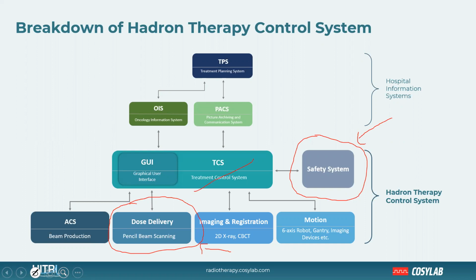Even if TCS crashes, for example, these two would monitor if the doors are open or closed, what's the currently delivered dose, whether it has already reached the prescribed level or not. And even inside they have redundant 2 ionization chambers, just in case one would give erroneous feedback. They have 2 either CPUs or 2 chips that kind of monitor everything. So this is kind of a simple answer. So when it comes to real-time delivery of the dose or even motion, you don't want to rely on particularly high-level software, but you want to do it with hardware devices on a lower level.